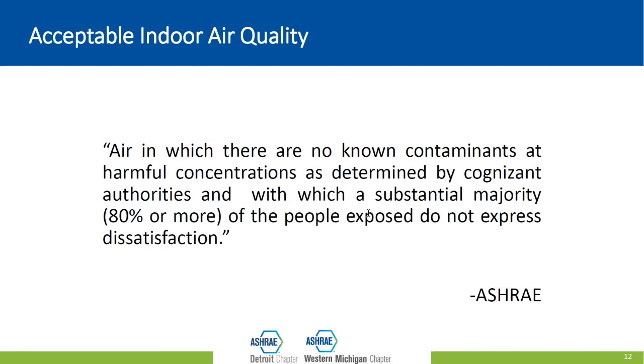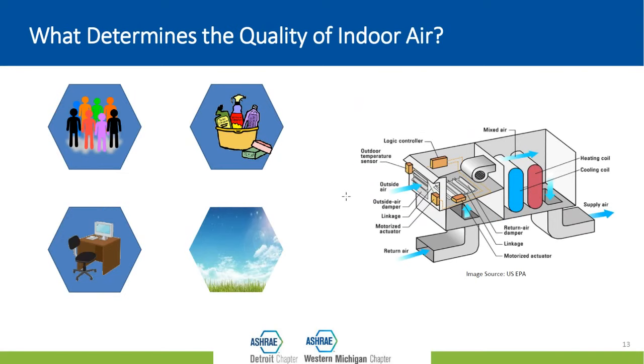Next slide. So what do we mean when we say acceptable indoor air quality? Well, ASHRAE defines acceptable air quality as air in which there are no known contaminants at harmful concentrations and with which 80% or more of the people breathing it are satisfied. So where does this air quality come from? Next slide. Well, it comes from us. People come into our spaces and they may be wearing cologne, they may be producing bioeffluents, they may have colds or other viruses that they bring in with them. Our buildings are full of furniture and equipment like desks and carpets and drapes that may be off-gassing some of the chemicals used in their manufacture. We may be performing tasks like welding or woodworking that generate dust. We may be cleaning and have chemical solutions in our spaces. And we come in from outdoors. We've got dirt on our shoes. We open doors that allow in pollen and insects.